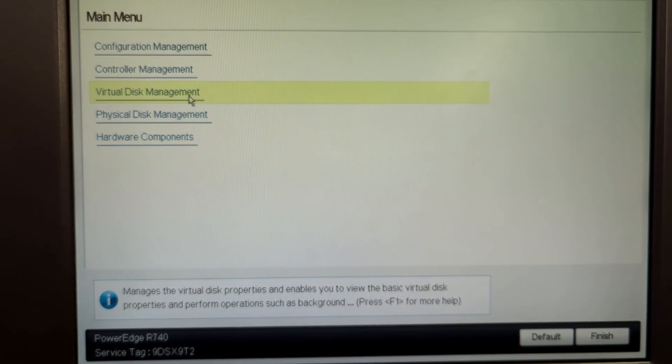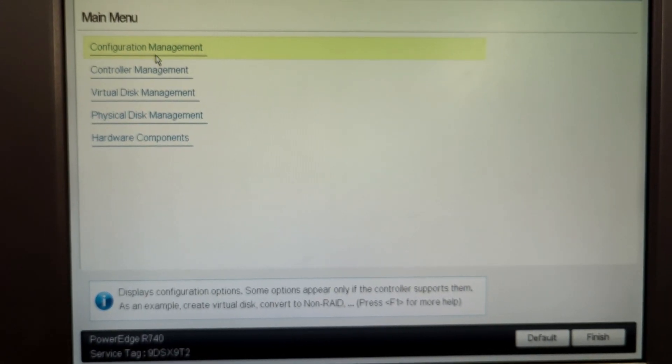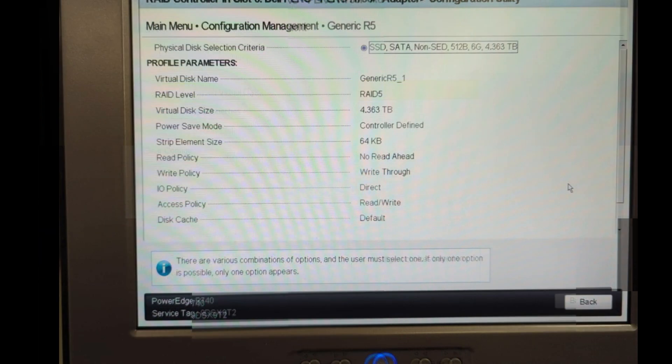Now let's create one more virtual disk for the remaining six virtual disks which I have. You can click on create profile based. The reason I chose create profile based was because this option gives me the ability to choose a hot spare with RAID 5. Because while RAID 5 can handle one disk failure using parity bits, it runs in a degraded state until the failed drive is replaced. With a hot spare, rebuilding starts automatically, reducing downtime and the risk of another failure before manual replacement. This option was quite useful, so I needed it. That's why I chose create profile based.